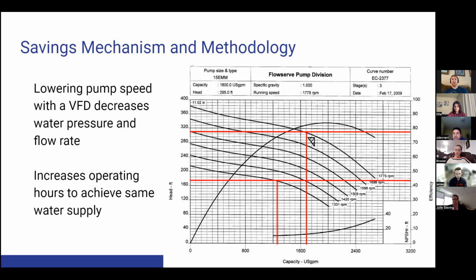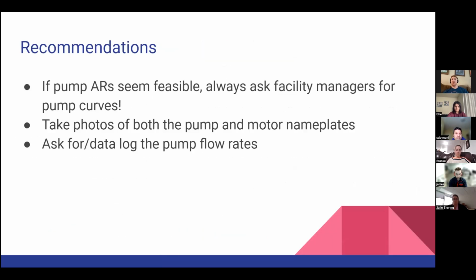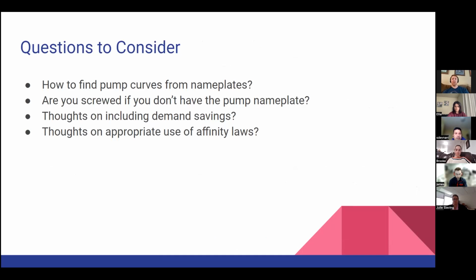Let's go back to your questions. Okay. How to find pump curves from nameplates? Get the model number, get the serial number, look up online or call up the manufacturer and they will give it to you. The beauty about model numbers is you'll find that information online invariably, even if it's a 20-year-old pump. Now, if it's a 40-year-old pump, you're going to struggle, but for a 20-year-old pump, from the turn of Y2K onwards, you've got data archived online.